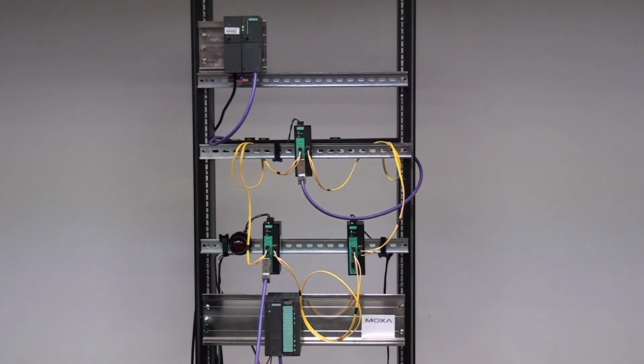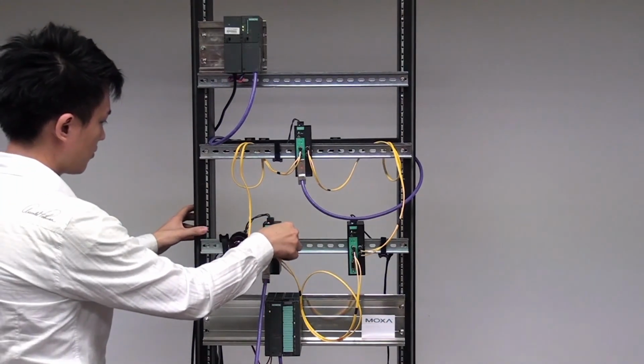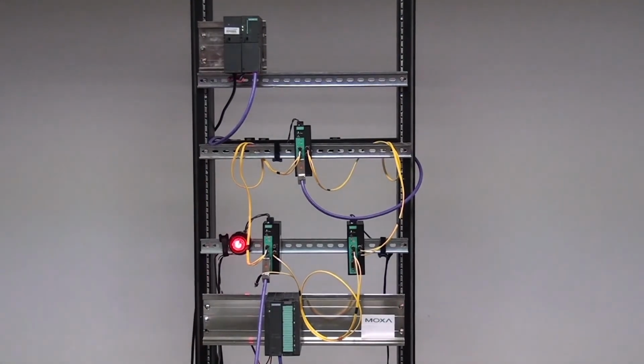However, the PLC is only able to detect an error when the PROFIBUS traffic has stopped completely, which means that the PLC will be blind to any cable failures such as this one because communications are continuing down the backup line. Luckily, with fiber diagnosis, the ICF1280i can step in.